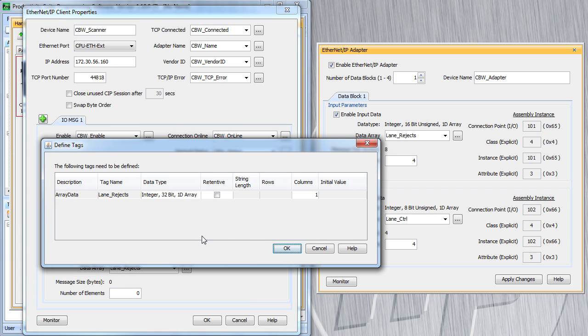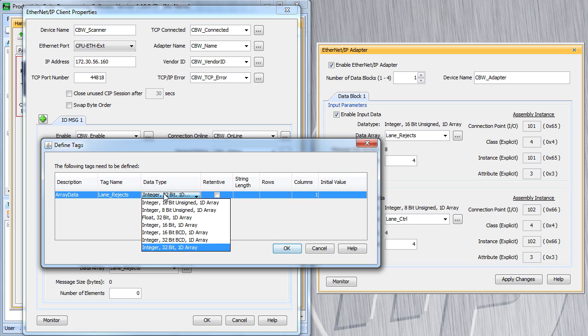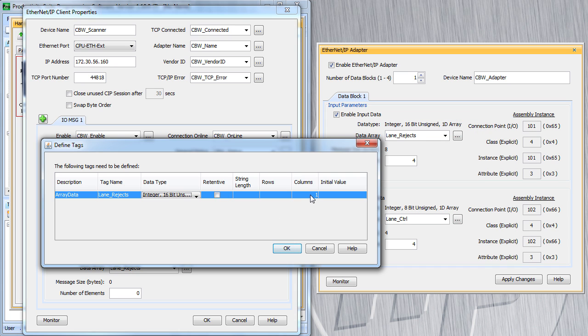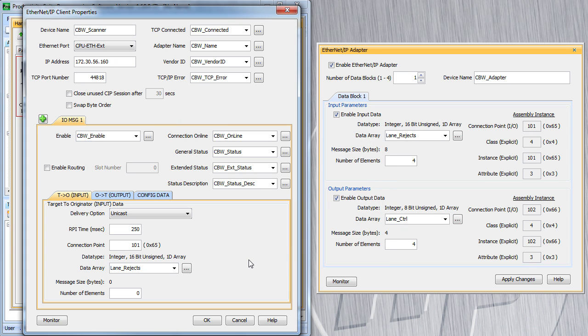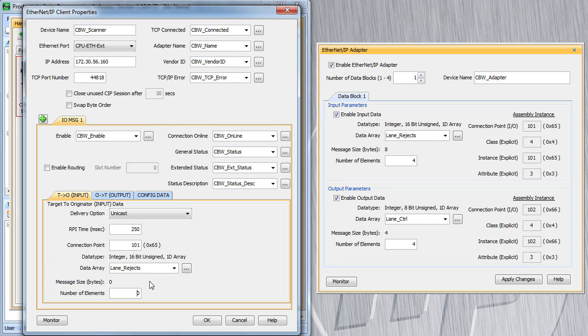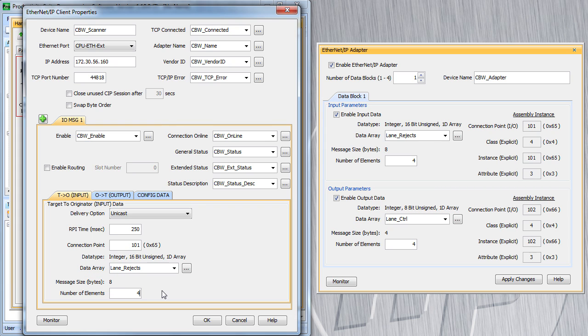This would be my Lane Rejects – as soon as I click away from that, the software comes up with a dialog that says, hey, you haven't defined that Lane Rejects array yet, what do you want to do with that? I want that to be identical to the array down here on the adapter. That was an unsigned integer 16, so I grab unsigned integer 16. I remember that he was 4 elements large, so I make my columns 4. So again, Unicast, 4 messages per second, connection point came straight from the adapter, I created a new array which looks just like the array down on the adapter, and all I have to do now is say how many elements do I expect? I know the adapter is sending 4, so I put a 4 here. And you can see the dialog is telling me that that means 8 bytes will be sent because those are 16-bit elements. This was the data going from the adapter – the candy bar wrapping machine – to us.